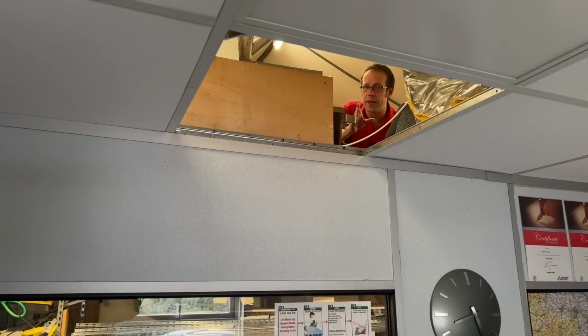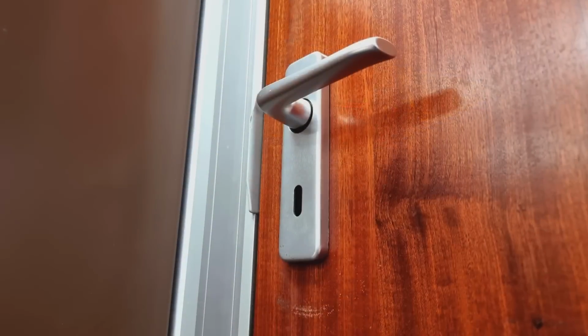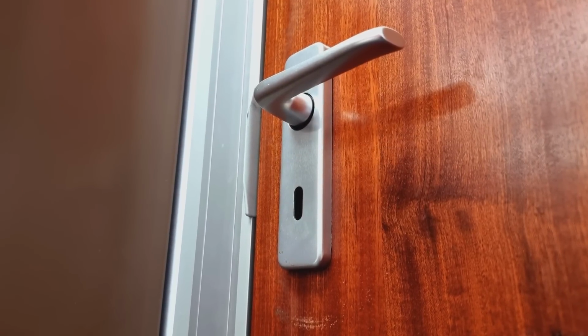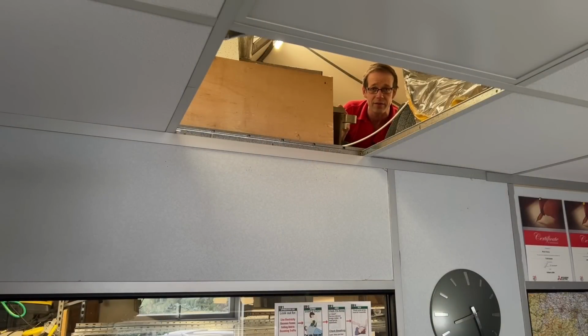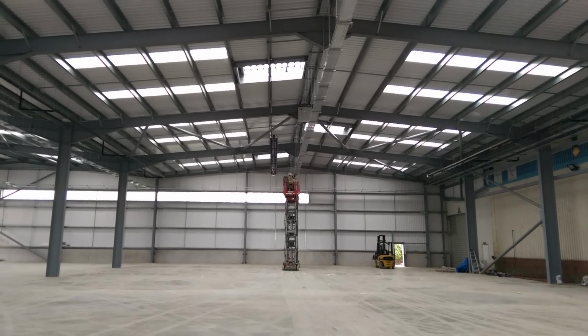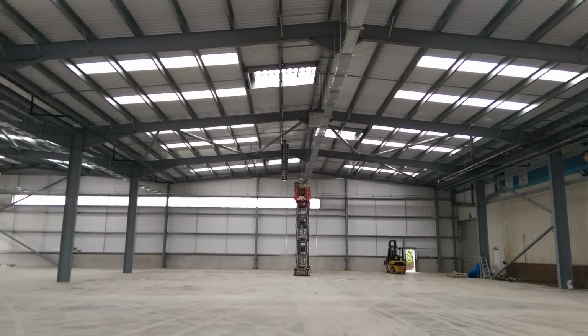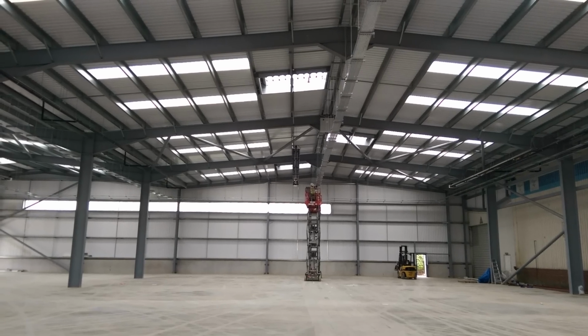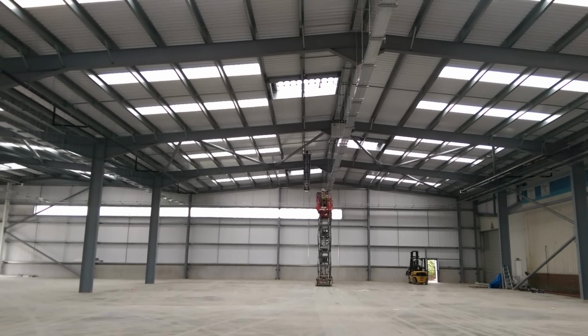Now, that is a thought-provoking question and it did give me pause. I know, they still look like hands, but it's kind of a trap to think this way because you could end up thinking about this endlessly. So what if the cables got knocked by the forklift and came to rest on a metal door handle? Someone on the other side could have come along and touched the door handle and got a shock. So should we have connected the door handle to earth? It's a bit of an extreme illustration, but it makes the point that actually what would have been better would be to think about the installation and the risks to the cabling. So at the design stage, it should have been identified that a forklift truck was to operate in that area, and so additional mechanical protection was required for the cables, or perhaps an alternative route should have been found for them.